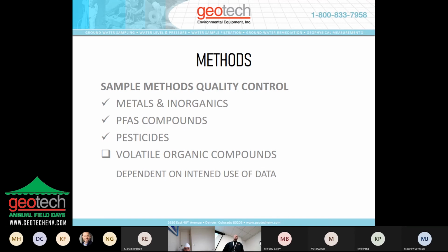It's great for PFAS compounds because once again, it's only touching the tubing. And as long as the tubing is correct for PFAS sampling, it can be used. If you're using a submersible electric pump for environmental sampling, most commonly they have Teflon parts in them and wear parts. So that could be a concern if you're doing PFAS sampling. Pesticides, once again, you're sampling with just the tubing. Only the tubing is in contact with the water. You have no worries about the pesticides leaching in or chemicals leaching out and contaminating your sample.